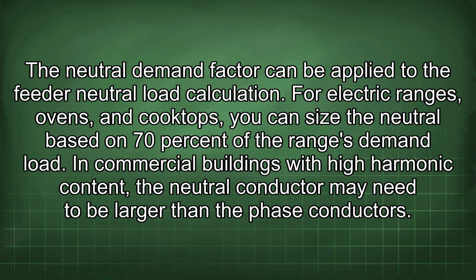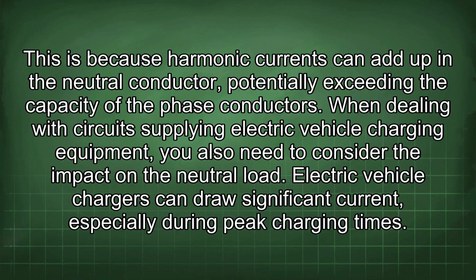The neutral demand factor can be applied to the feeder neutral load calculation. For electric ranges, ovens, and cooktops, you can size the neutral based on 70% of the range's demand load. In commercial buildings with high harmonic content, the neutral conductor may need to be larger than the phase conductors. This is because harmonic currents can add up in the neutral conductor, potentially exceeding the capacity of the phase conductors.